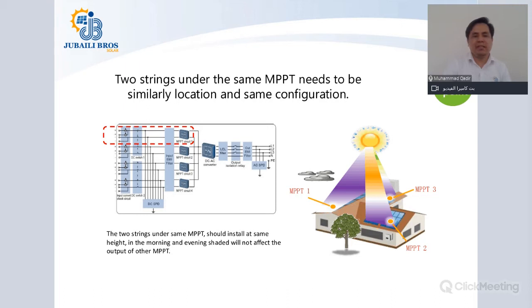Two MPPTs should have string connections in a way that either both have the same orientation or different orientations. But strings connecting to one MPPT must be facing the same orientation. Therefore, this slide stresses the point that two strings under the same MPPT need to be in the same orientation and same configuration. So if two strings into the MPPT1 are with a 10-degree tilt, yeah, that is good that you have taken care of the direction and the tilt angle.